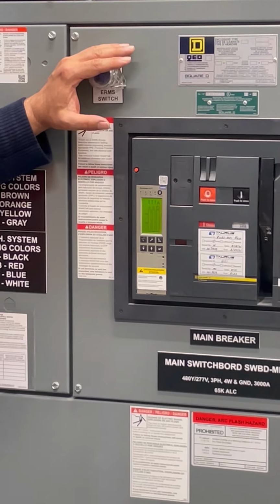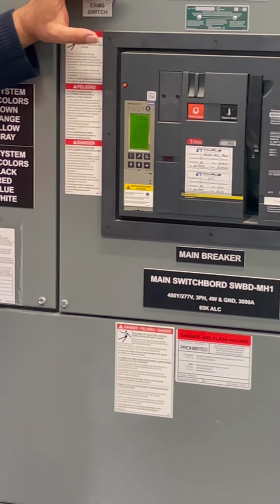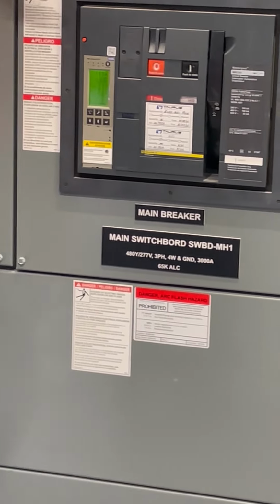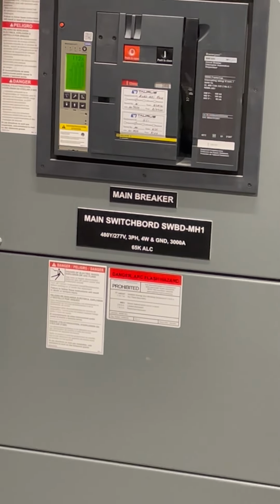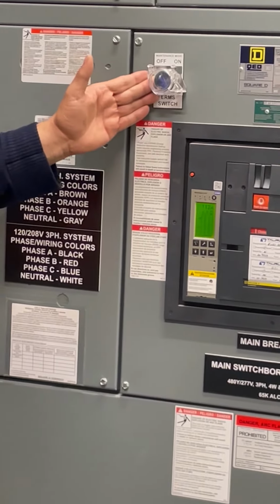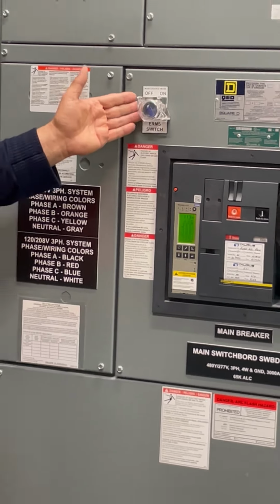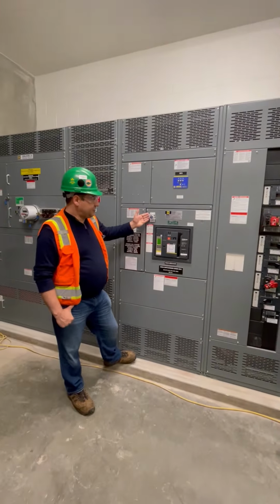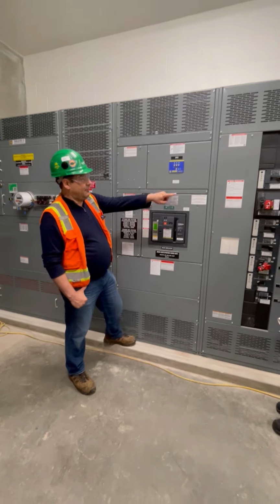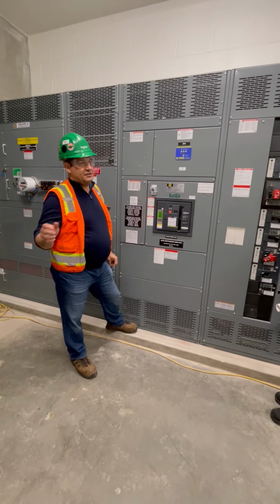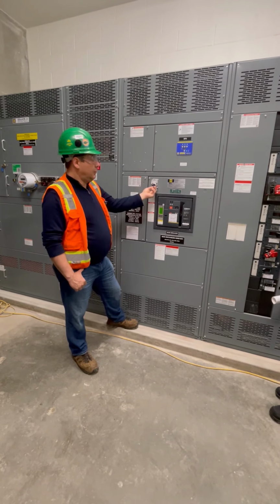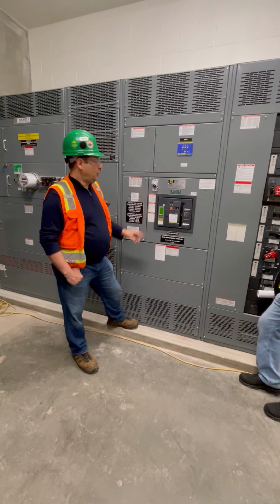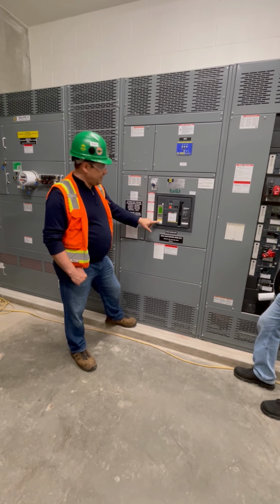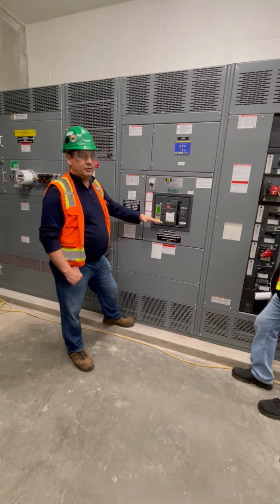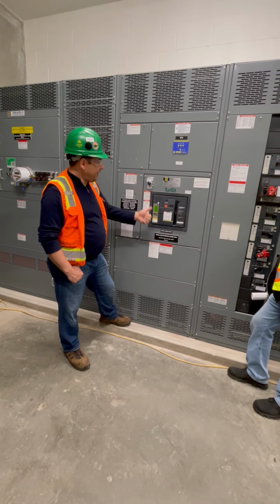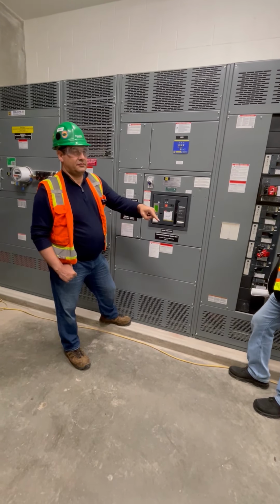In a study that Lee had referenced, you should have two tables. One table is when you operate under normal conditions, which means this is in the off position. It's not recommended otherwise; it has to be operated in the off position, and then those labels and everything apply. But in the studies, there should be a label when this thing is in the on position. What that means is all the settings in here go down to the lowest possible settings, which means the breaker trips faster and reduces your arc flash downstream.